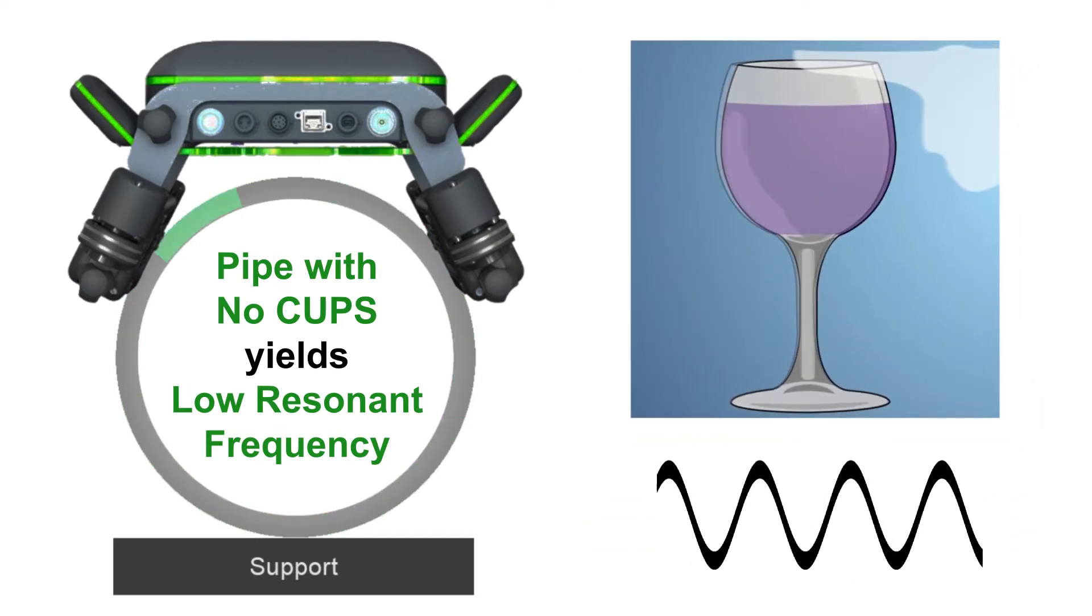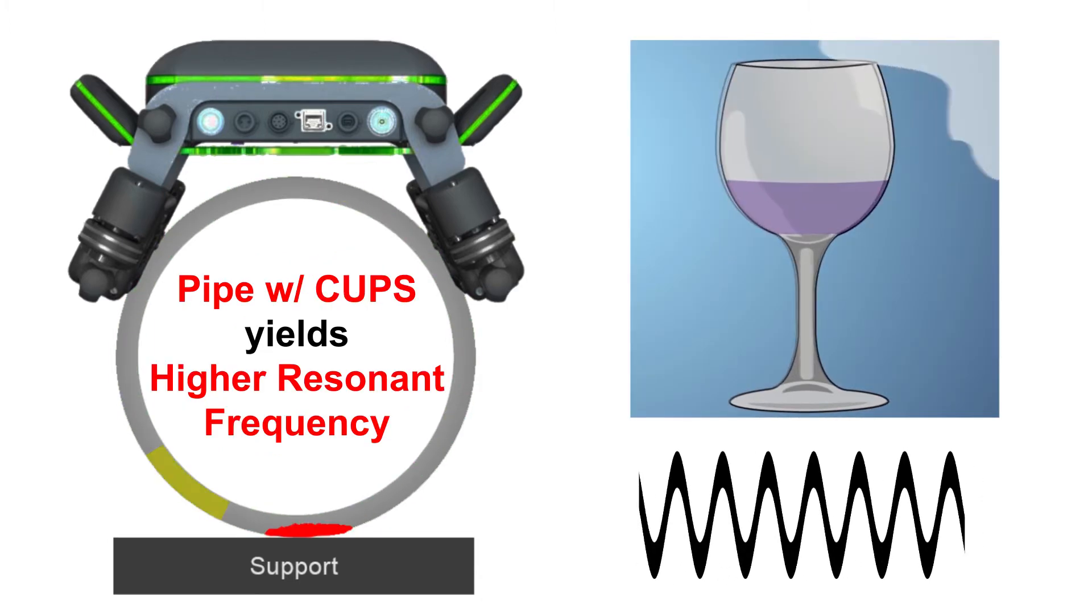On one hand, a pipe with no corrosion under pipe support is analogous to a full glass which yields a low resonance frequency. On the other hand, a corroded pipe is analogous to a half-full glass which yields a higher resonance frequency.